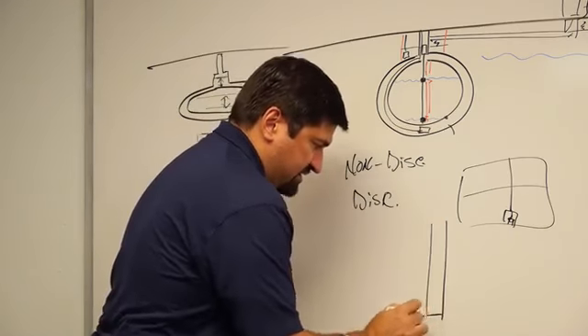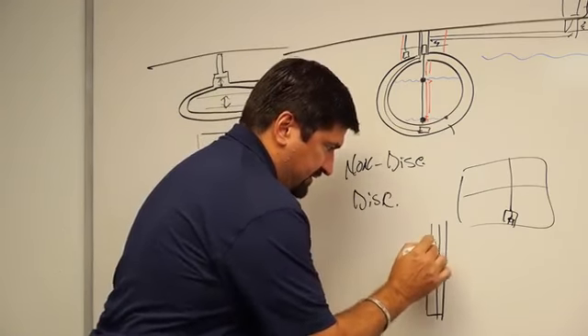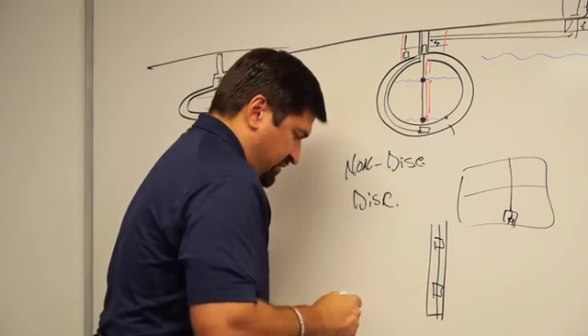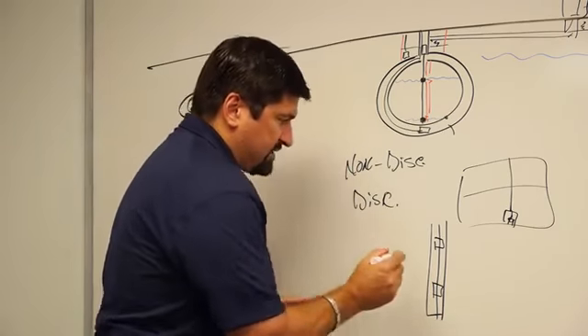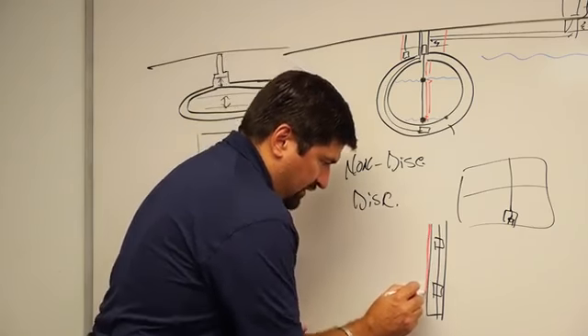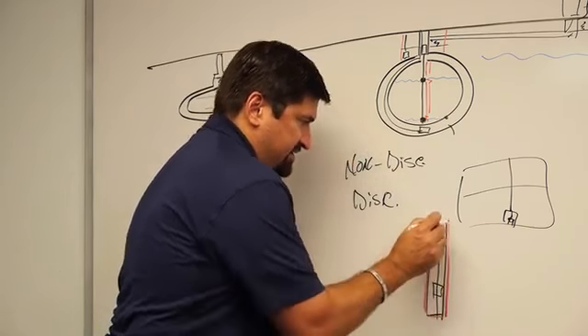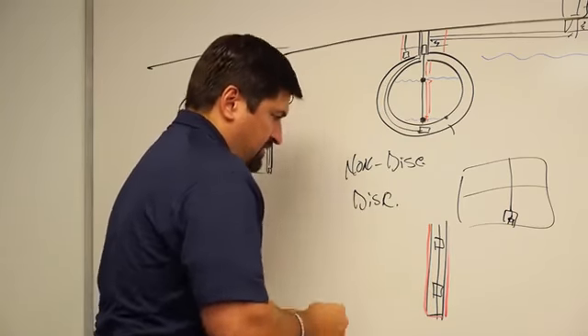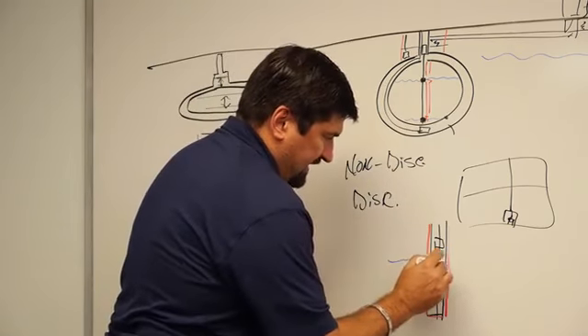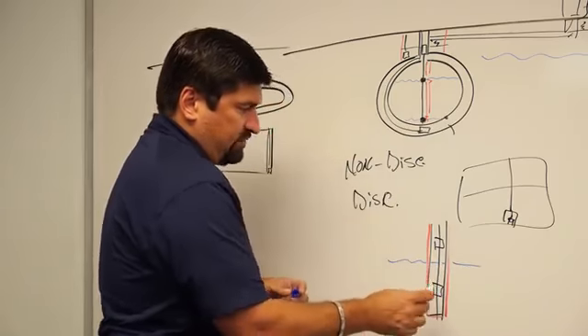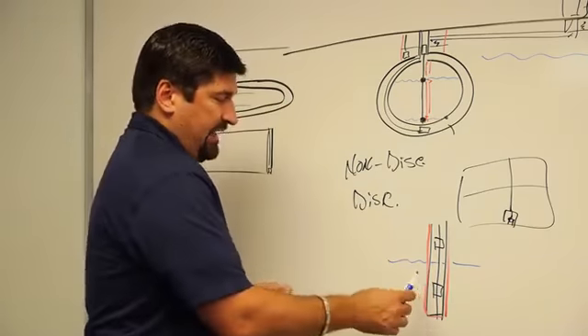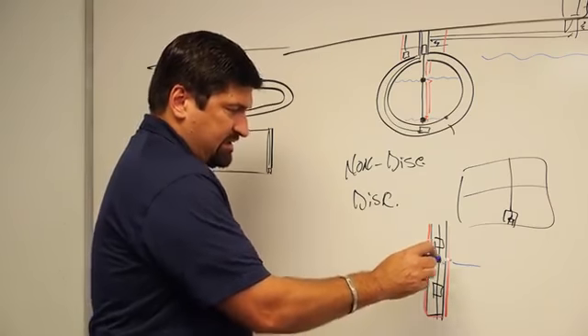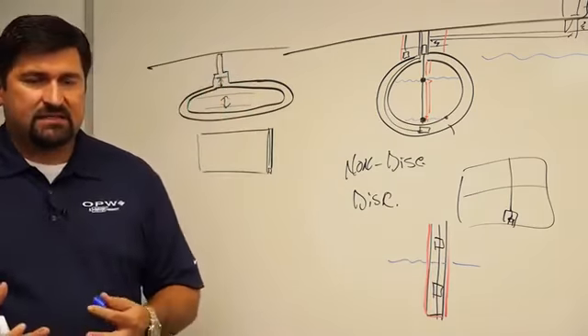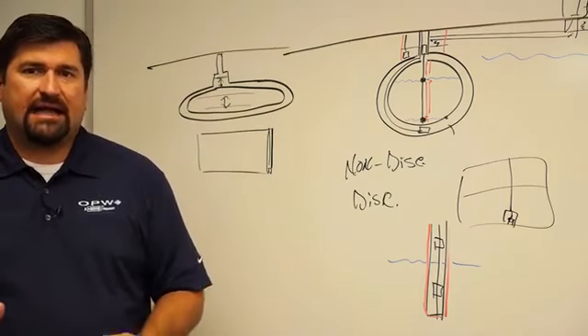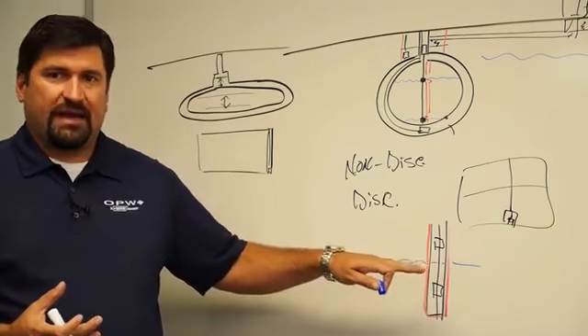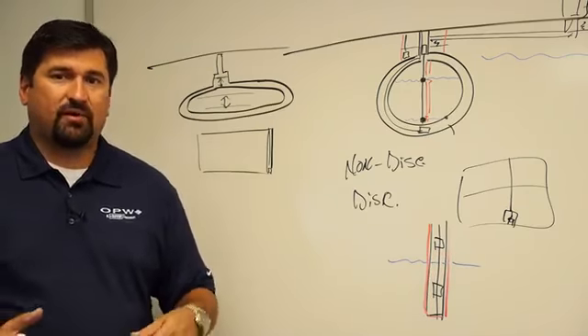When you start looking at discriminating sensors, we have the same thing with a float, but in a normal sensor, what you would have is the little floats, but what you would also have is a polycarbon band that would go along the outside of the sensor, so that if water or fuel came into contact with that band, it would lift this float, letting you know that there is a liquid there, that it is present, and then at that point it looks at this polycarbon band. Well, the band is designed to actually expand when it comes in contact with fuel, increasing the resistance of the band, letting you know that that is either hydrocarbon or water.